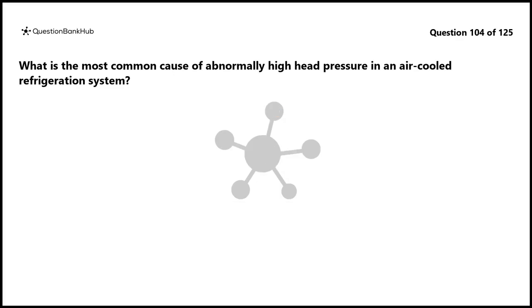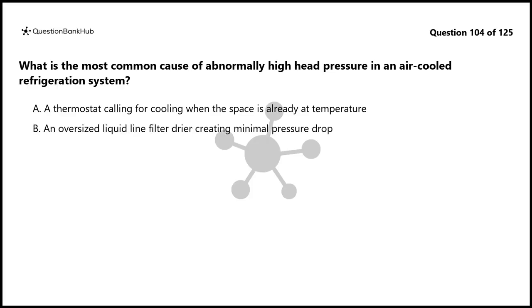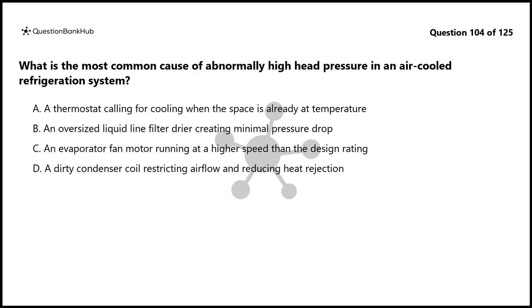Question 104. What is the most common cause of abnormally high head pressure in an air-cooled refrigeration system? A. A thermostat calling for cooling when the space is already at temperature. B. An oversized liquid line filter dryer creating minimal pressure drop. C. An evaporator fan motor running at a higher speed than the design rating. D. A dirty condenser coil restricting airflow and reducing heat rejection.